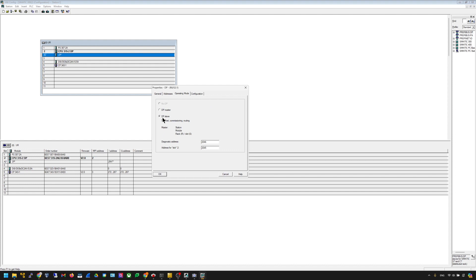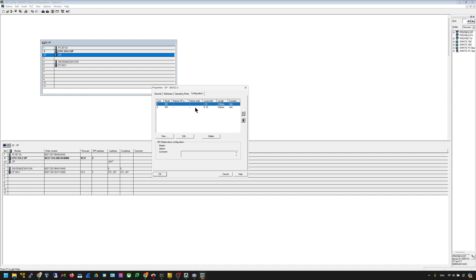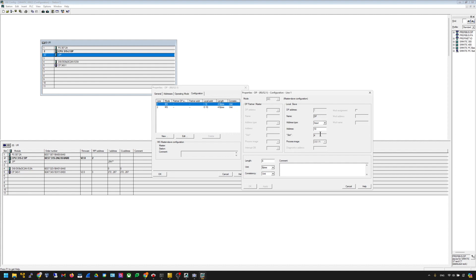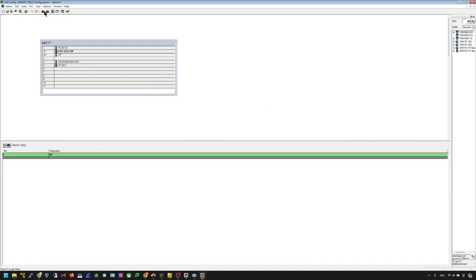Go to Operation Mode and make sure it is set to DP Slave, because the EL6731 will act as the Profibus master. Then go to Configuration. Here you can configure each slot — what kind of data it handles, input or output. Slot 1 is configured as input for 4 bytes starting from local address I10. Slot 2 is configured as output for 4 bytes of data. You can double-click to choose input type and address. To add a new slot, click New. After completing the configuration, download the project to your Siemens PLC.